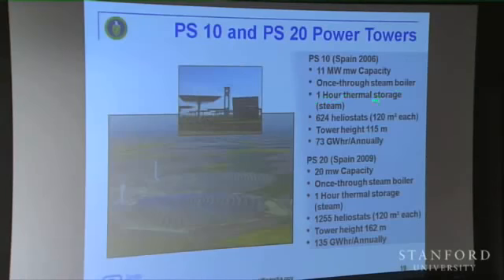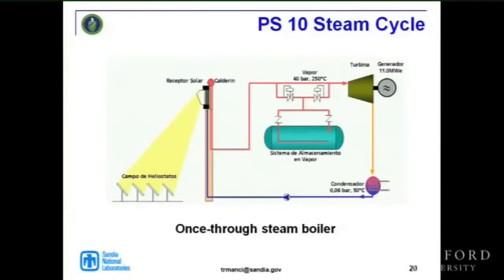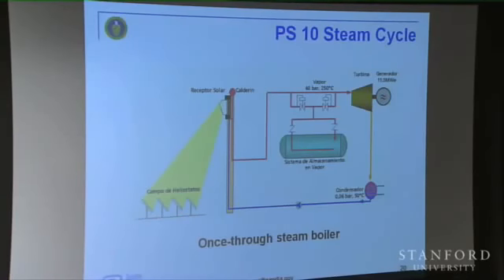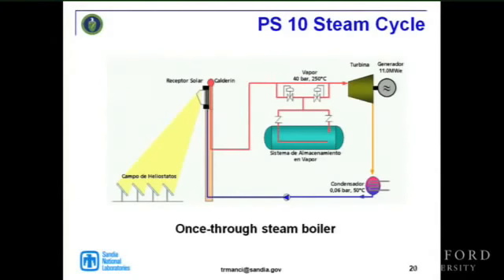The way they operate is they pump water through the receiver to generate steam, then use that steam to drive the turbine. They also store a little bit of it to get some steam buffering, and steam storage is very expensive to do, but they do it to mitigate some of the intermittencies they have. The solar regime in Spain is generally lower than what's available in the southwest U.S.—about equivalent to West Texas, actually, which I always found interesting. The system pumps water through the receiver, generates steam, and either sends it to storage or directly to the power block. This storage is rather expensive because it's hard to store high-pressure steam for any length of time, and the cost of the tanks is relatively high.